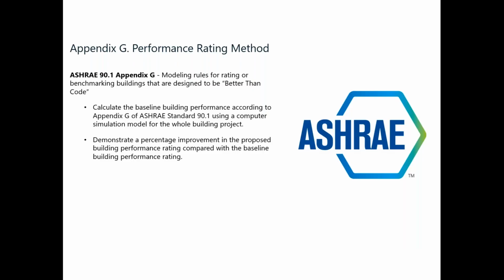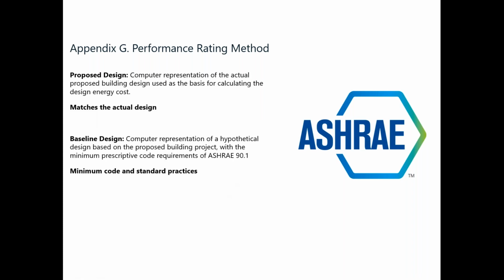We generally almost always follow 90.1 Appendix G. Nearly all our schools in the Mid-Atlantic are LEED schools of some shape or form, whether designed to that standard or achieving it. In Washington, it's a requirement, and we're generally following 90.1 Appendix G for our performance rating when evaluating systems. What's important is that we talk about a proposed design and a baseline design. The proposed design matches the actual design on our construction documents, and the baseline design, for the most part, is minimally code compliant and standard practice per ASHRAE 90.1. We're constantly comparing those two.